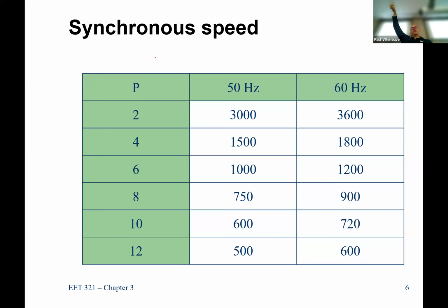For me this direction is counterclockwise, this is clockwise, but either way it always spins at that speed. In 60 hertz land, it runs at 3600 RPM. If I double the number of poles, now I'm at 1500 and 1800, then 1000, 1200, 750, 900. Remember we talked about hydroelectric facilities where they can't have high speed — you need a lot of poles to get from point A to point B.